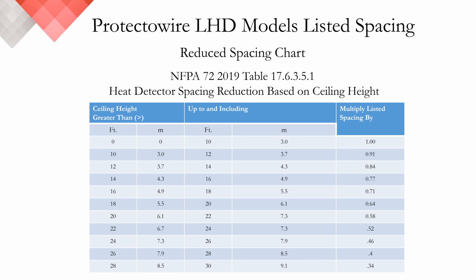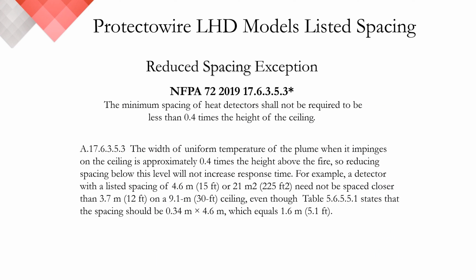However, when the ceiling exceeds this 30-foot threshold, the spacing reduction formula converts from a factor of the listed spacing to a factor of the actual ceiling height. We receive a lot of questions asking if linear heat detection can be installed on ceilings 30 feet or higher, and the answer is yes. At heights above 30 feet, Chapter 17 refers us to the reduced spacing exception, stating, the minimum spacing of heat detectors shall not be required to be less than 0.4 times the ceiling height.